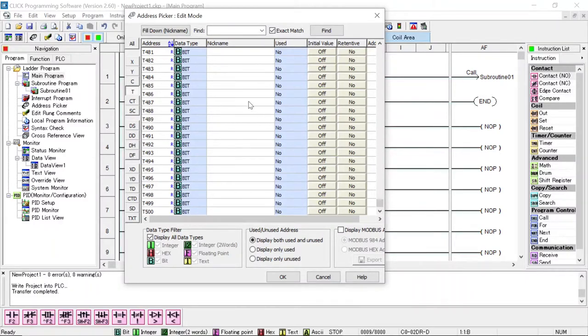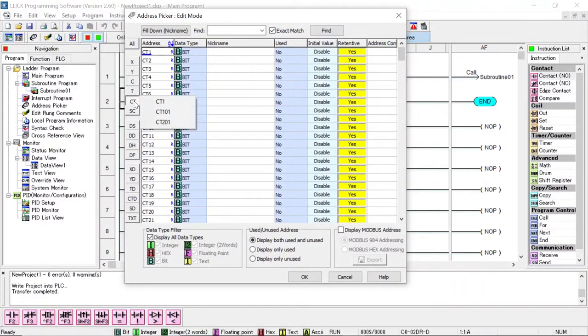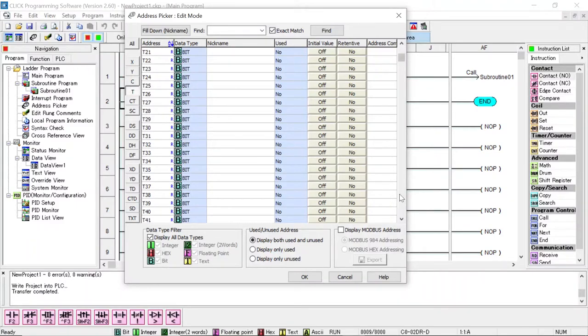When you have that many, the numbers don't really mean anything. We need a name or something that helps us keep our heads straight when we're trying to work through the program. All right, next we have the CTs. The CTs are counters. And you can see the numbering system goes just like it does on the timers. It just continues, just normal base 10, all the way up to 250. We can have 250 counters. And as we said before on the timers, we could have 500 timers. So that's a lot of timers, and that's a lot of counters, a lot of information that you can keep up with. And when you're trying to program that much, it's very, very important that you have nicknames for these timers. For example, this timer 485, maybe you would use that one and you would call it left turn timer Elm Street East, for example. Because if you just have it going 485, you're looking at the program and your eyes just start to cross.